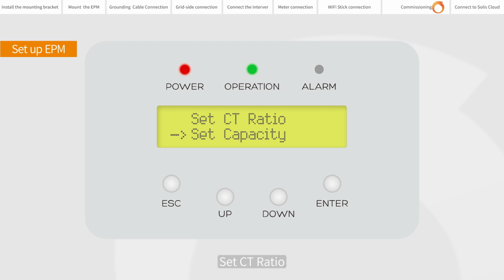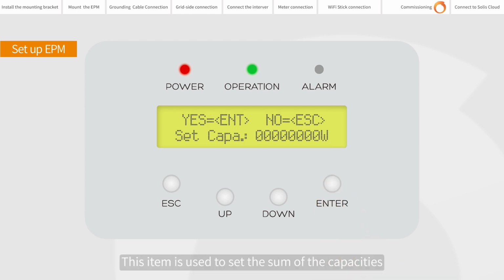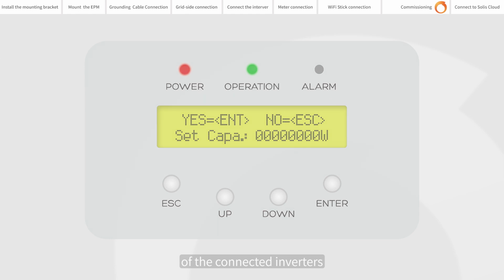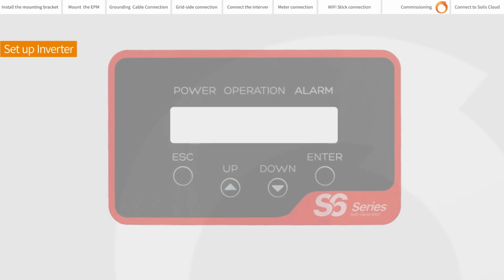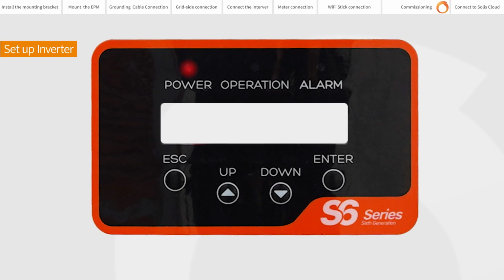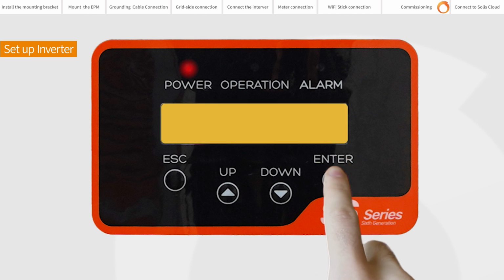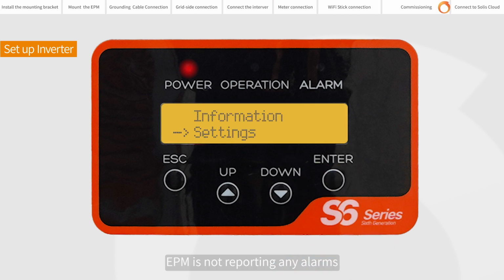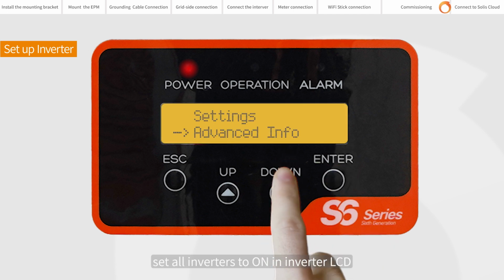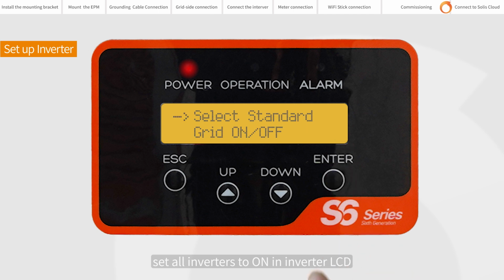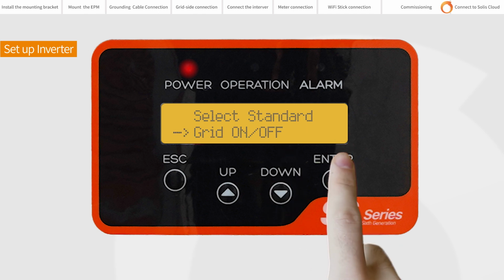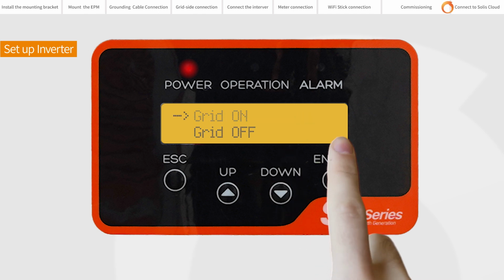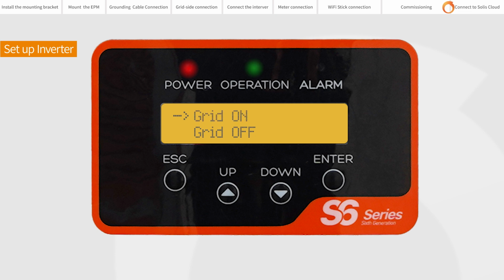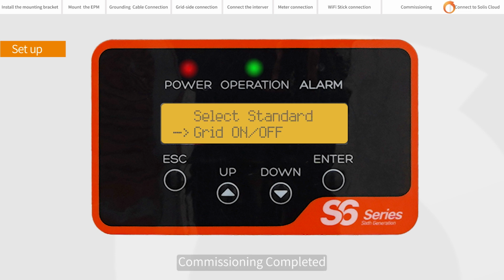Advanced settings, set capacity. This item is used to set the sum of the capacities of the connected inverters. EPM is not reporting any alarms. Set all inverters to on in inverter LCD. Commissioning completed.